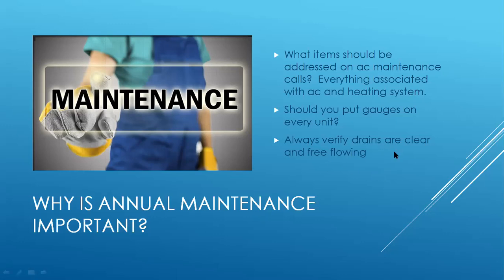So also when it comes to drains, there's nothing worse than Bob went out there and did a tune-up. 2 weeks later, John's out there and you've got a backed up drain, water everywhere. Drains don't back up that quick. And a small drain backup can easily lead into a $10,000, $25,000 water claim. And if you get a couple of those on your insurance policy, your liability policy, it goes up very quickly from there. So always make sure your drains are clear and free flowing, which I'll get into in a little bit on that.